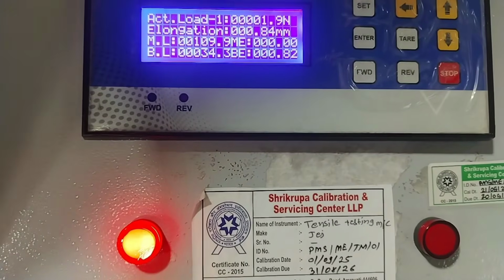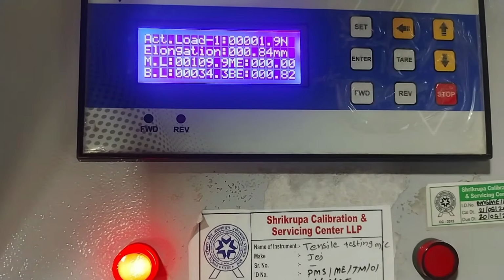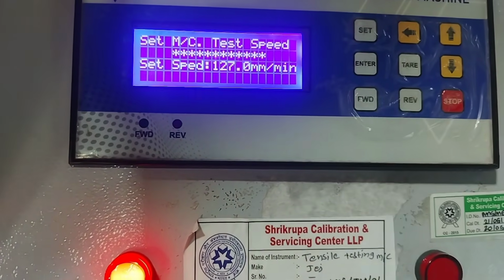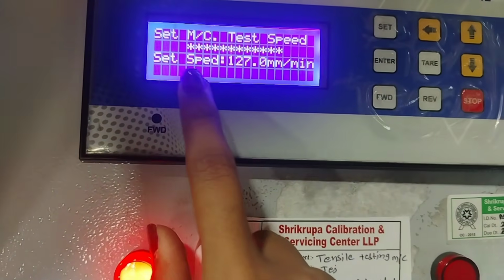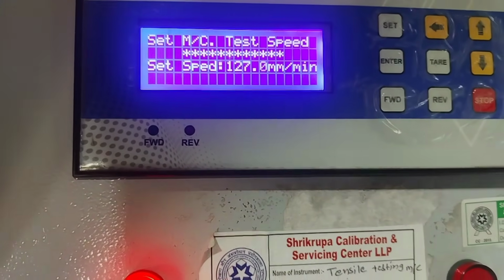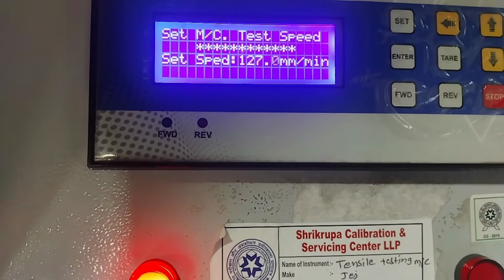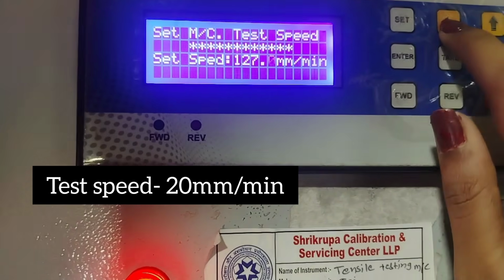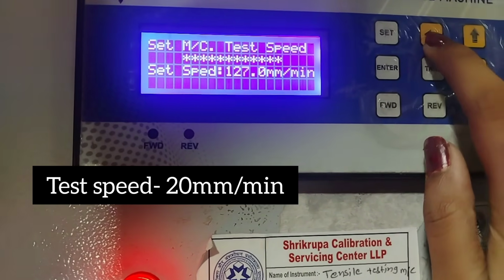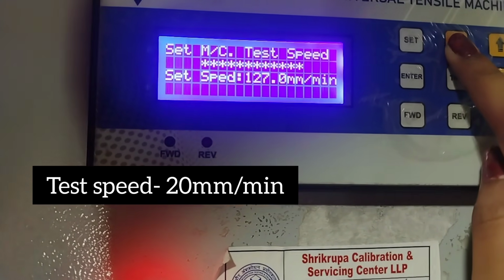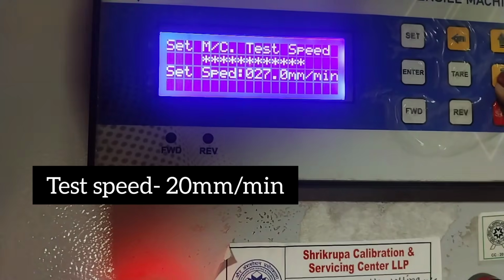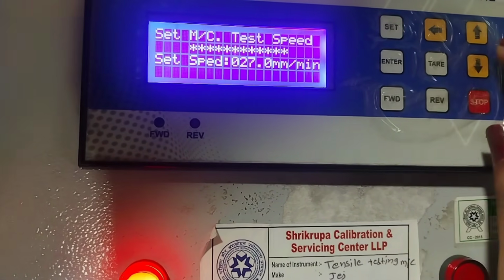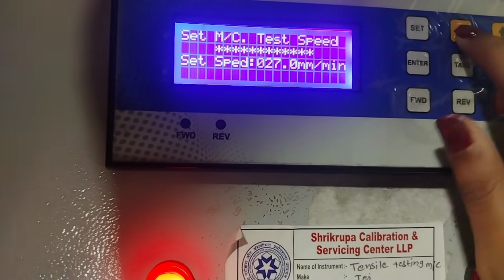Now let's see the settings on controller. Here is the set button. Here we have to set test speed. For geomembrane, as per standard, the test speed is 20 mm per minute. So just click on the arrow and set the speed.